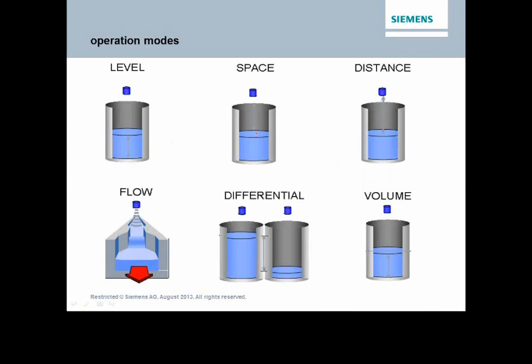We do space measurement, which would be from the material surface to some given point above the material surface. And then lastly, a distance measurement, which is actually our transducer face, our flange face, to the material process. This is important because when we have conversations, quite often what we're looking at is setting up for a level application, but we're actually doing commissioning and setting up. We go into distance mode so we can confirm our measurements. When it comes to using alternate technologies like ultrasonics, we get into flow, differential, and volume calculations as well.